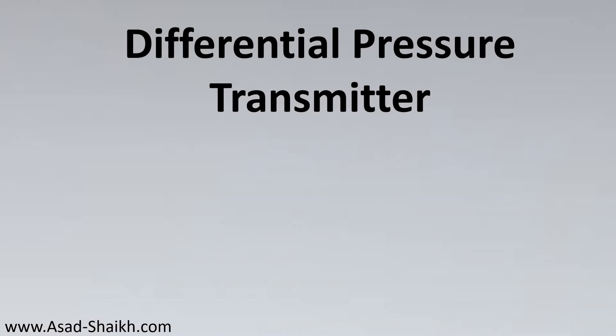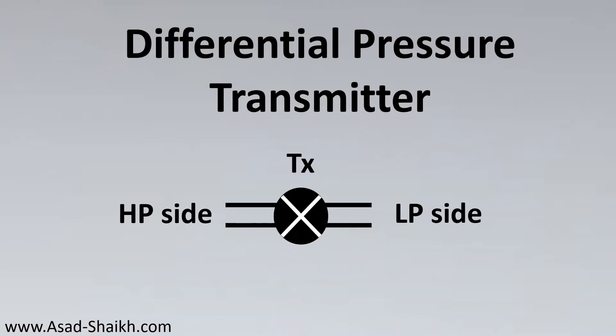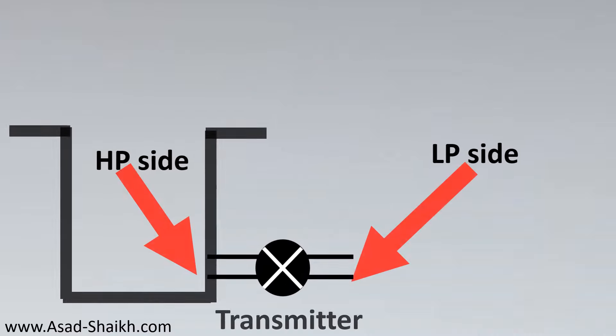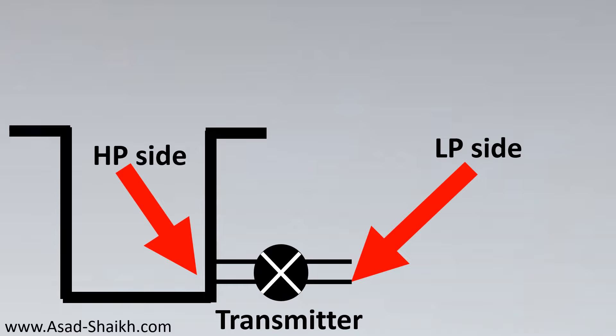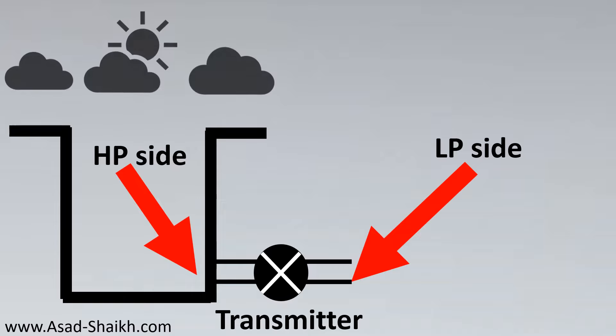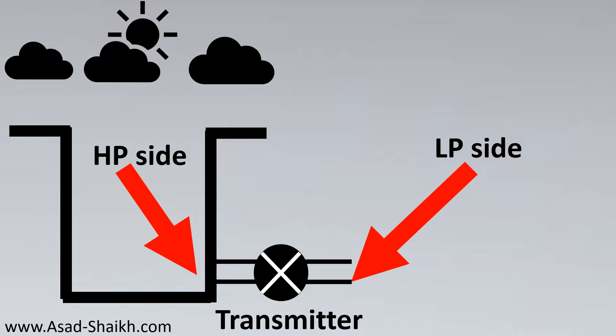Here is our differential pressure transmitter. It has the HP side and the LP side. This is how it gets connected to the tank. The HP side, as the name suggests, would be connected to the side where there is the highest pressure, and the LP side is kept open to atmosphere because this is an open tank. Had this been a closed tank, the LP side would have been connected to the top of the tank.